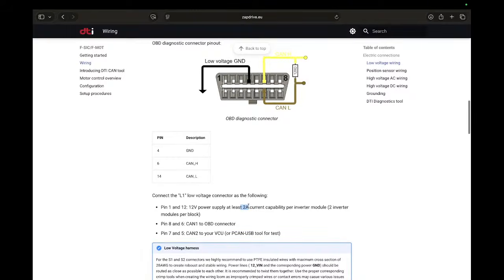This doesn't mean you need the whole 4 amps of current rating during operation, but during a startup sequence you will need more current draw than during normal operation. This is why we require at least 2 amps per inverter - it's a requirement to operate stably. Otherwise the power supplies within the controller unit will not start up properly, and it will just get stuck in a boot or something else.